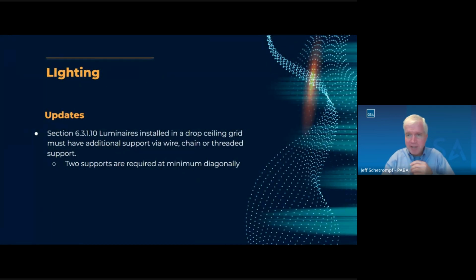And then one last thing for lighting, it has to do with supporting the fixtures in drop ceilings. So we're now requiring at least two supports on a diagonal axis back to the building structure. In many states, this is a requirement for seismic or firefighter safety. It's generally a default in our project specs as it is, but we know it's not always universally happening on all our projects. So we've added it to the P100 to help make sure that it does happen as we roll forward. So that kind of closes out our lighting section here.